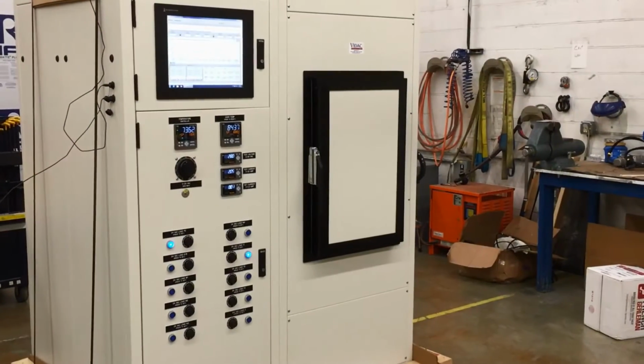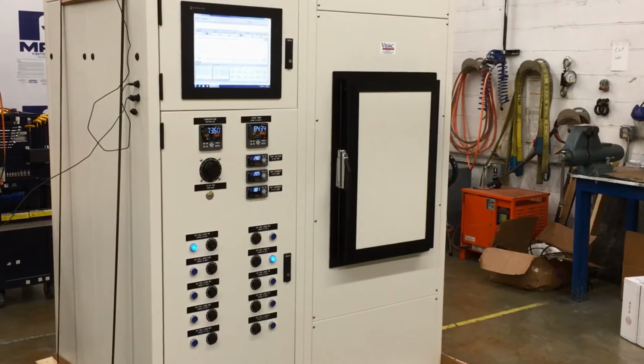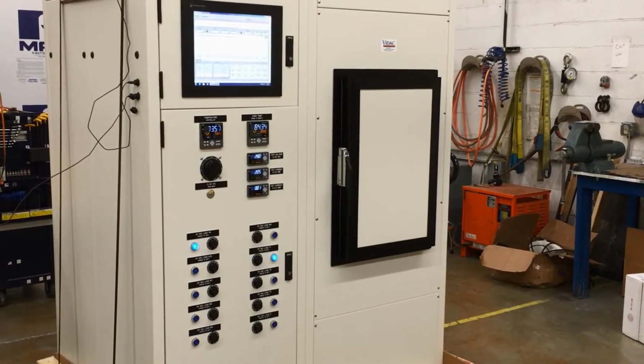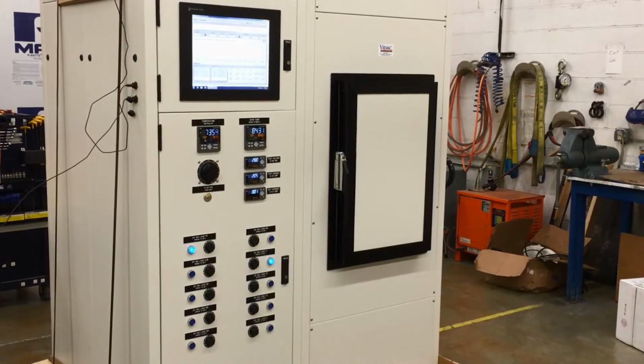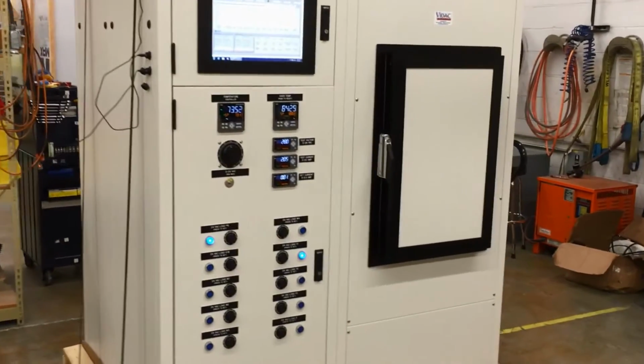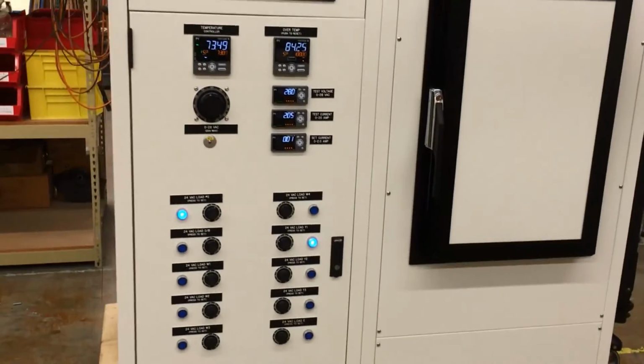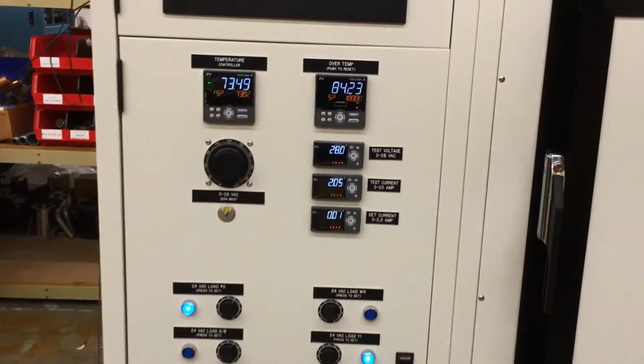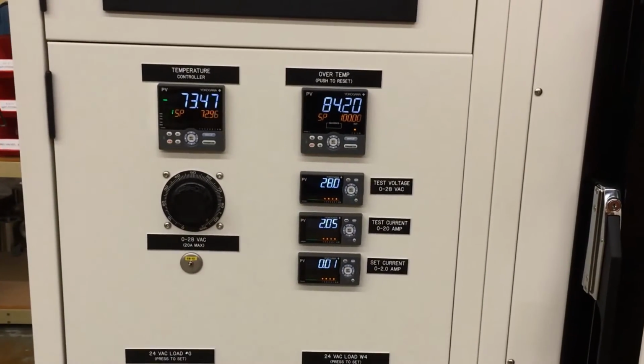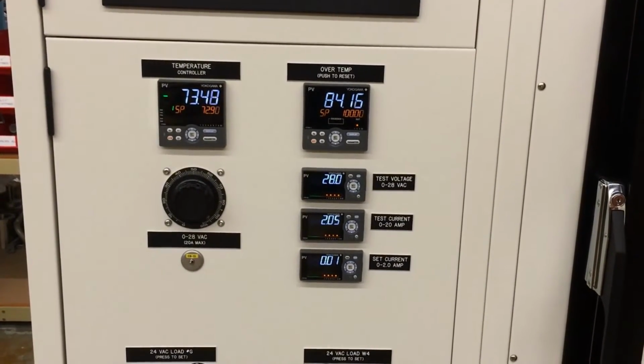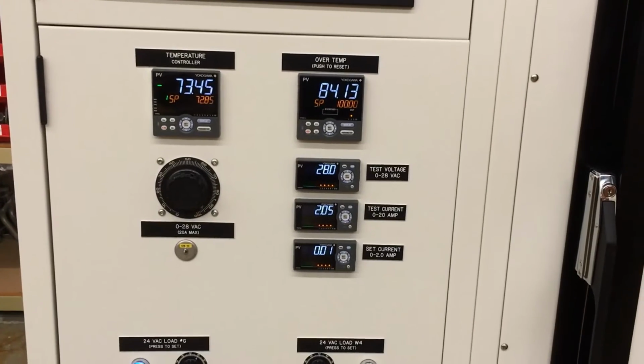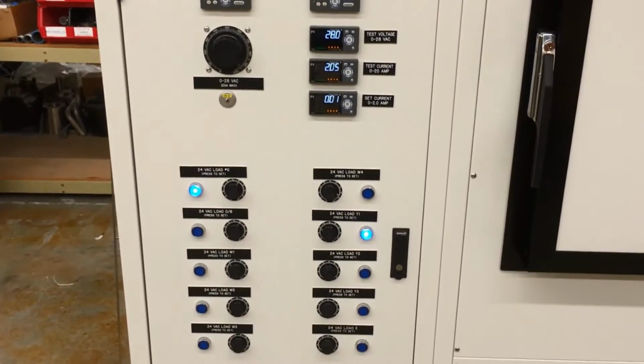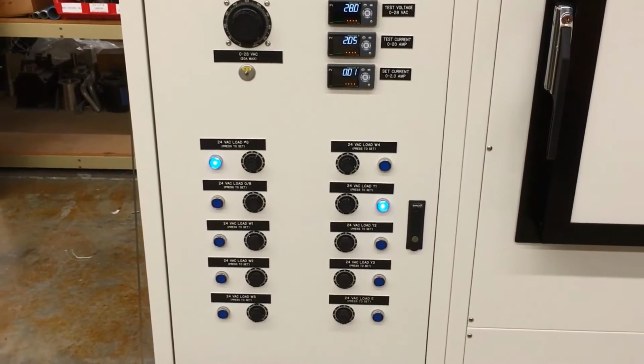Here we have a NEMA DC-3 thermostat test chamber that we're doing final inspections on before shipping out. I'll just walk you through the operation of this really fast. First of all, we use Yokogawa temperature controllers to maintain very tight temperature control. It's currently coming down from a very high temperature soak to verify operation.